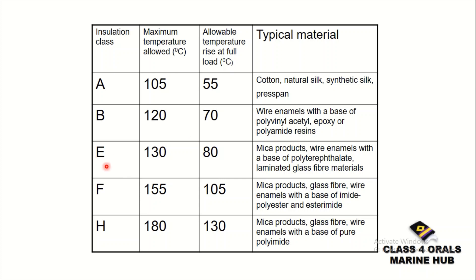Next, Class E insulation. The maximum temperature allowed is 130 degrees centigrade, and at full load the temperature rise is 80 degrees. Typical materials are mica products, wire enamels with a base of polyvinyl acetylate, and laminated glass fiber materials.